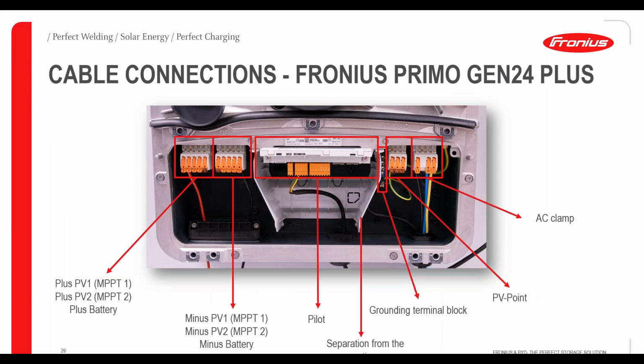We also made some adjustments to the connection area of the inverter. We put in clamps that you can remove from the inverter when installing cables. For example, if you're installing the DC side on the left, you can unclick the cable connection, stand outside the inverter to connect the cables, then click it back into the inverter. This is very good if you have a tight or dark area, as it lets you connect everything from standing in front of the inverter instead of in the cable area.